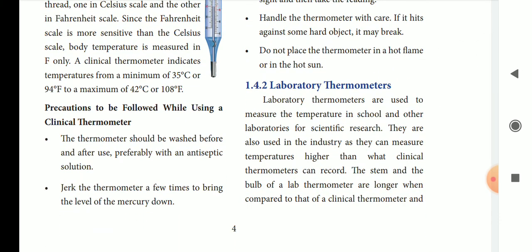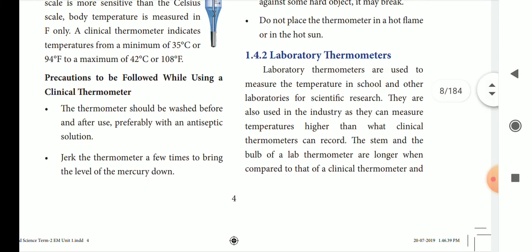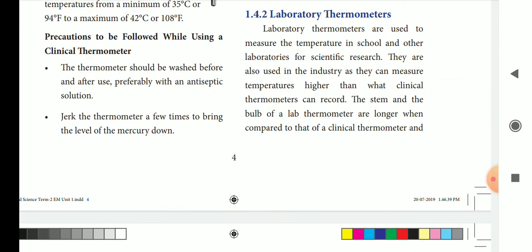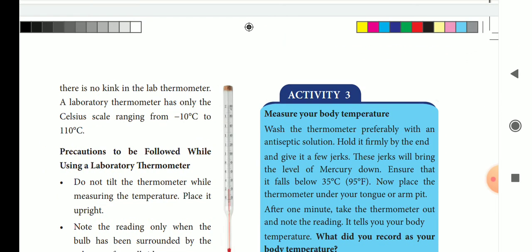Laboratory thermometer is used in the laboratory and industry. They can measure temperatures higher than what a clinical thermometer can measure. Clinical thermometer is used up to 42 degrees Celsius. The stem and bulb of a lab thermometer are longer compared to that of a clinical thermometer. There is no kink in the lab thermometer. The lab thermometer range is from minus 10 degrees Celsius to 100 or 110 degrees Celsius.